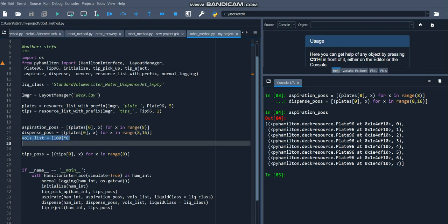Now we have to specify a volume list, and in this case, each channel will be aspirating a volume of 100 microliters. The volume list will be a list of length 8, where each element of the list specifies the volume being aspirated by each channel.